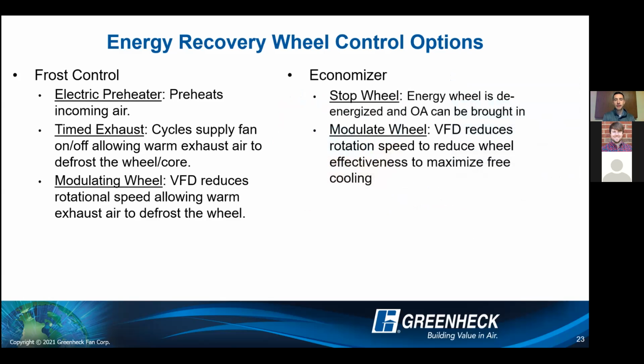And then from an economizer standpoint, we're really looking at two different options. You're going to stop the wheel or you're going to modulate the wheel. When you stop the wheel, it is doing what it says: the energy wheel is de-energized and the outdoor air is just brought in through the wheel. Obviously, no energy recovery is taking place. With a modulating wheel, we're just reducing the VFD speed to maximize the free cooling that we get, which is reducing the wheel effectiveness. So those are really the options that you'll see on this type of equipment.